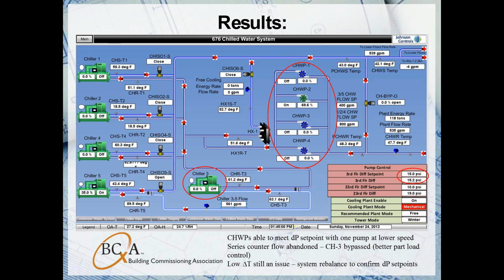originally designed. And obviously the things that we saw early on that Mark and the team saw: two pumps running instead of one, the differential pressure not being met. All those things are important takeaways as we talk about the plant. If you see those, those are all clues and keys, if you're getting into an existing building commissioning project, that you need to be looking for and get to the bottom of solving.